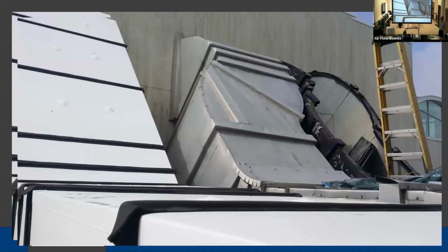Now I want you to take a look at this. This is a job that I think is in Indiana. We are in mid-construction on a duct replacement. You can see we've got the insulating tape. I just want you to imagine the job that this contractor originally did, this ductwork failed. They did an amazing job. Think of how hard the insulator worked to clad this ductwork. He covered every 4-bolt flange with a cover. It's insulated underneath. You had to kind of feather the bend here. You can see though that they had to put screws through it to get it to hold, and then those screws are all rusting and failing.